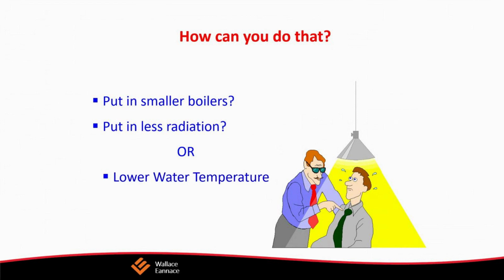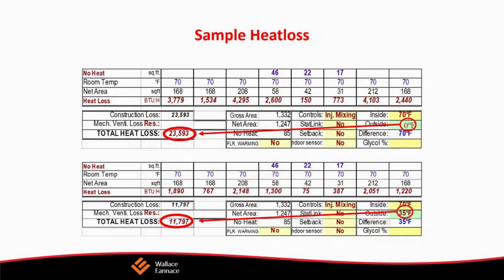So first thing you've got to consider, let's take a look at New York City. Typically when we design in New York City, we choose either 10 or 0 degrees as a design temperature. So we build a heating system at 0, for example, to heat a space when it's at perhaps 0 degrees. This is bin data from ASHRAE showing the number of hours that are spent at various temperatures in New York City.